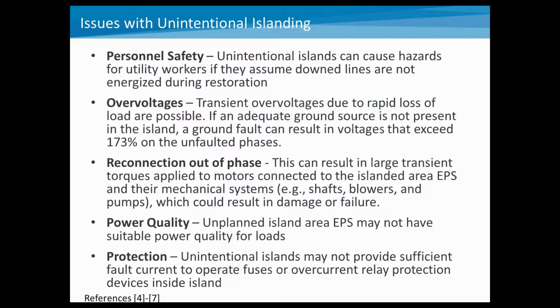And so what are the issues with unintentional or non-planned islands? First off, personnel safety. Unintentional islands, if they're operating, could cause hazards for utility workers if they're assuming that the power lines are not energized, for example, during restoration. So if you have distributed generation that is accidentally maintaining the power and voltage live on lines, that's a potential safety hazard. There's also the potential for overvoltage, both transient overvoltages due to the rapid loss of load if a breaker opens and you have generation on the islanded side. You may have a very quick overvoltage condition occur because of the loss of load.